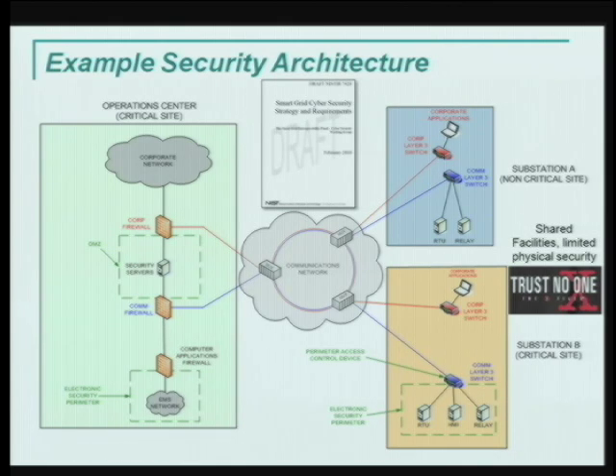Recognizing the importance of the energy management system - the SCADA network, for which the wrong button pushed on one console can black out an entire city or large area - particular attention is made to ensure it runs on a completely separate, physically isolated network in most utilities. Here it's depicted by the blue lines and blue ring, versus the corporate firewall shown as the red ring, with a lot of monitoring in place and mechanisms allowing specific corporate clients to access aspects of the energy management system through very controlled environments. There are as many versions of this diagram as there are utilities, and some utilities have multiple versions.